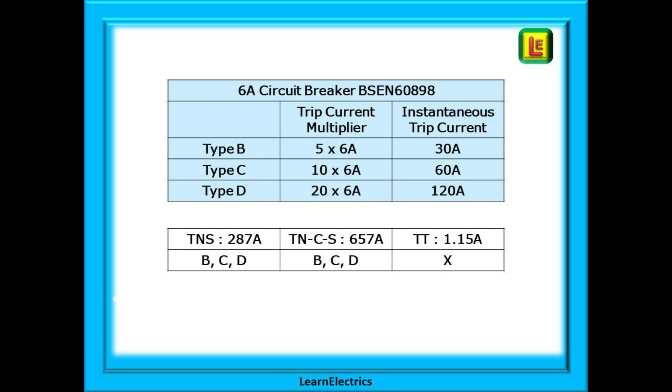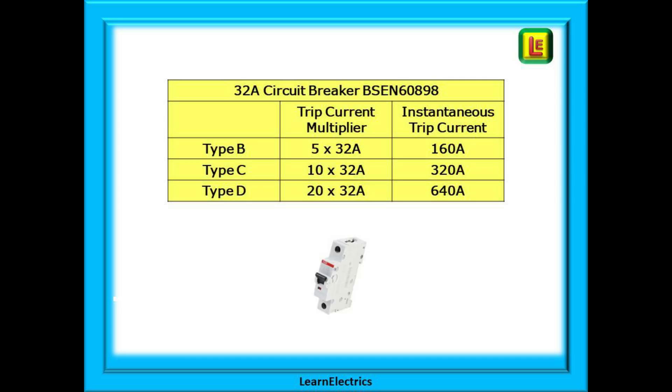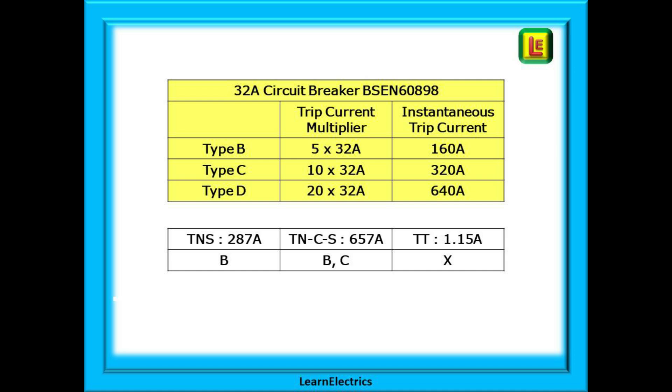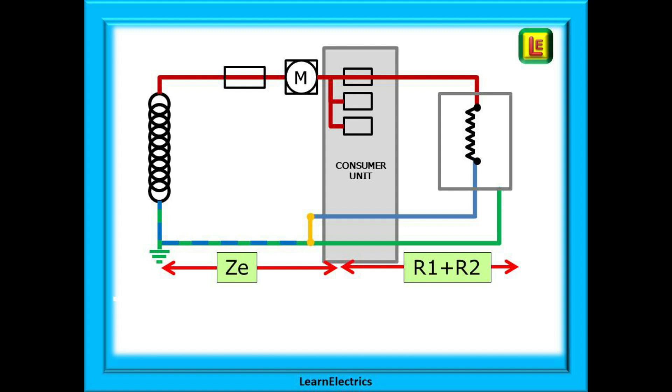Look now at a 32 amp MCB. It needs the same trip current multiplier 5, 10 and 20 times the rating but now the current is that much bigger. With the ZE maximum figures a TNS system at 287 amps will cause instant operation of the B32 breaker but not the C type or D type. For the TNCS system the fault current is sufficient to trip the B and C types in the required time but not the D type. And alas the TT system at 1.15 amps will never trip any of the breakers. To the TT system it's just another ordinary day.